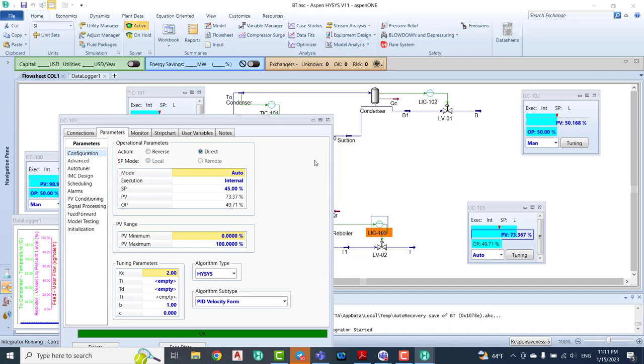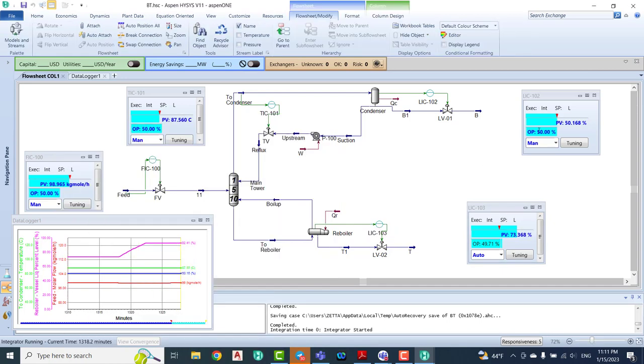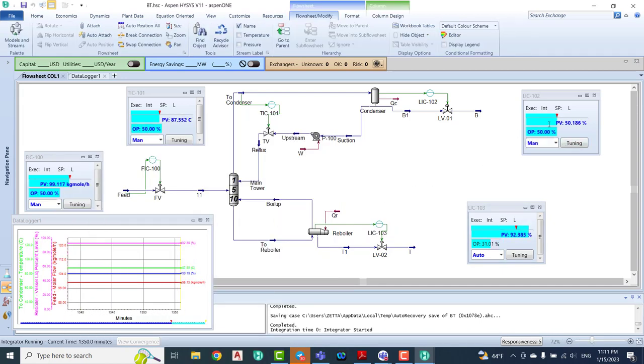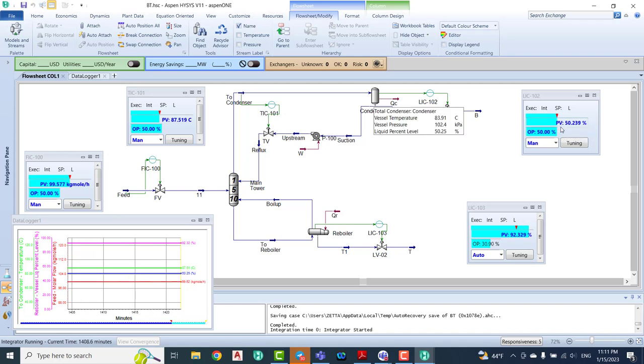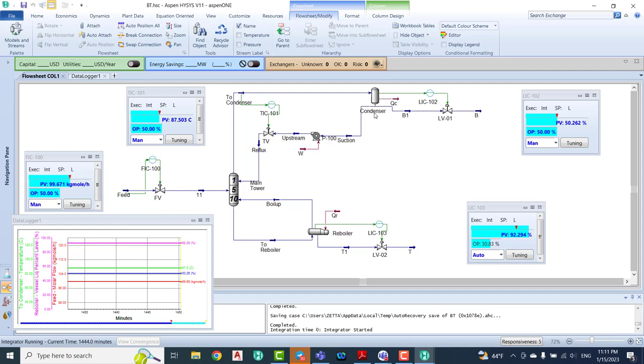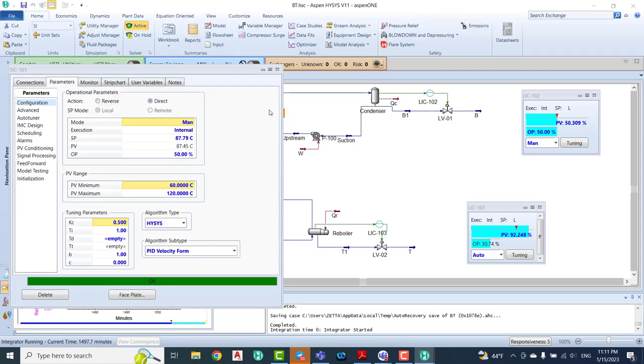Let's see in here. We have the PV, that means the level on the side of the condenser. We have 50, that means it's perfect, the level of the condenser. Now about the temperature, let's go inside the temperature.